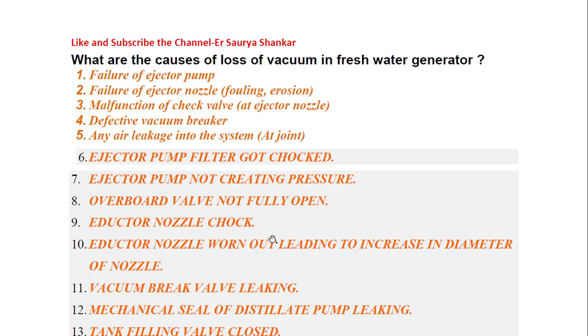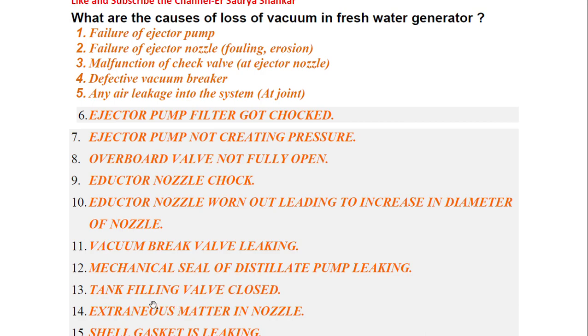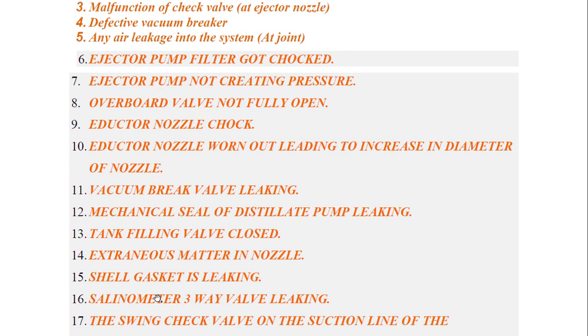Eductor nozzle choked — those previous points were regarding the ejector; this is regarding the eductor. Eductor nozzle worn out, leading to an increase in diameter of the nozzle. Vacuum break valve leaking, mechanical seal of the distillate pump leaking, tank filling valve closed, and foreign matter or deposits in the nozzle.